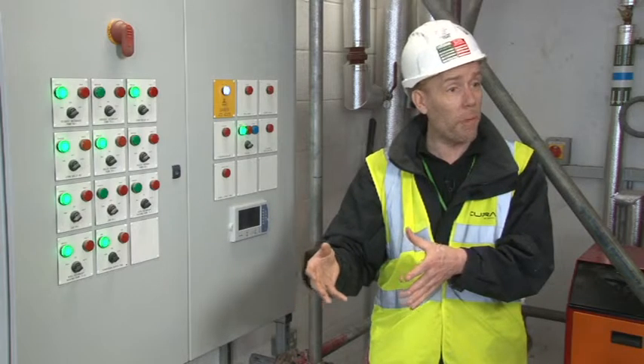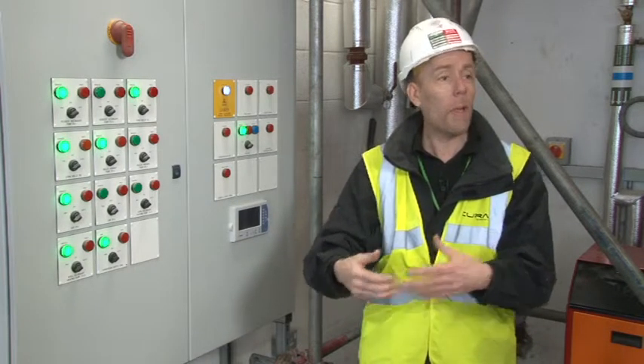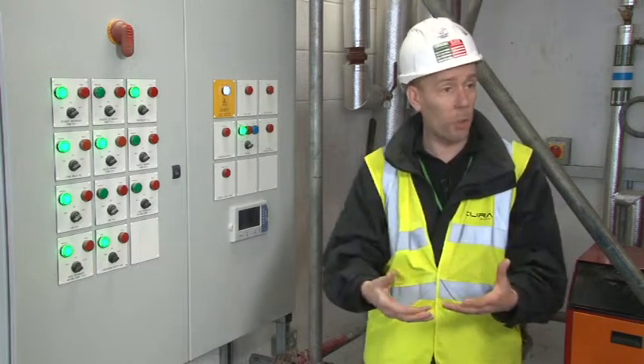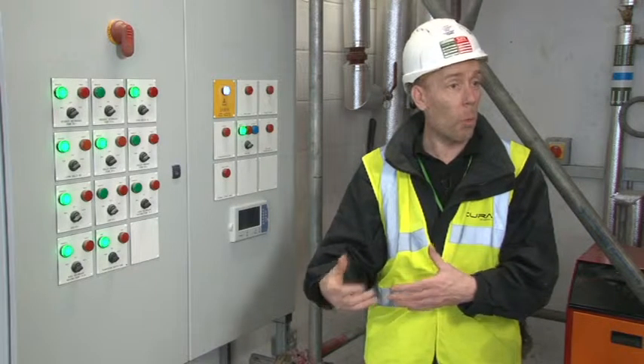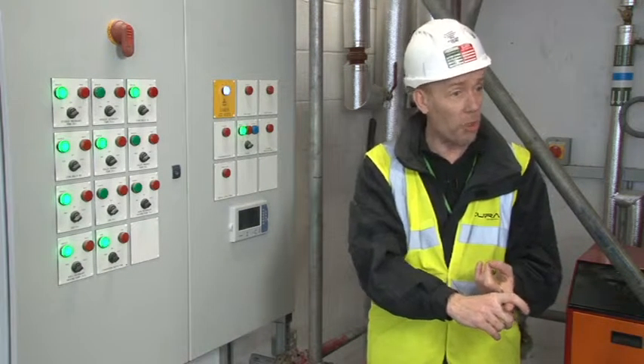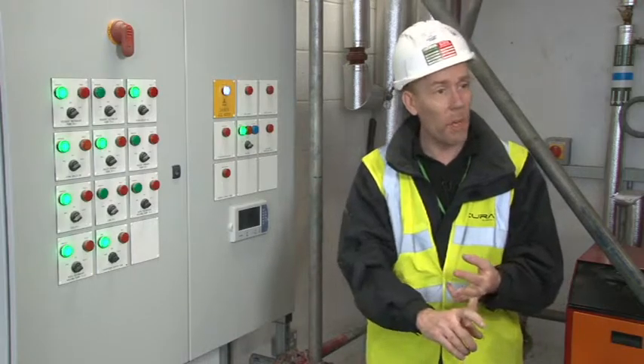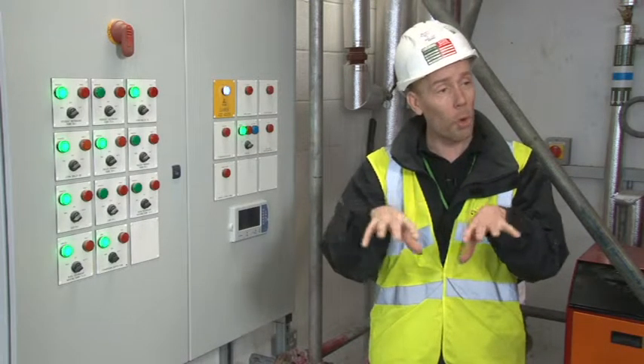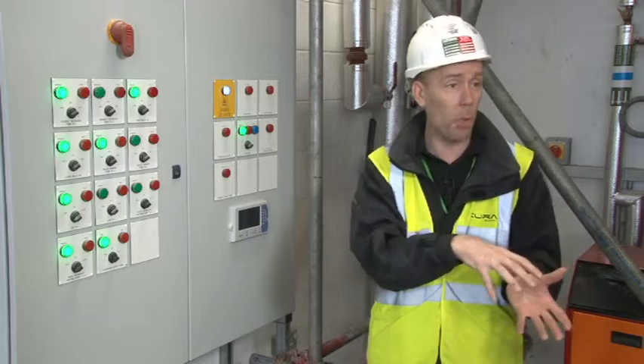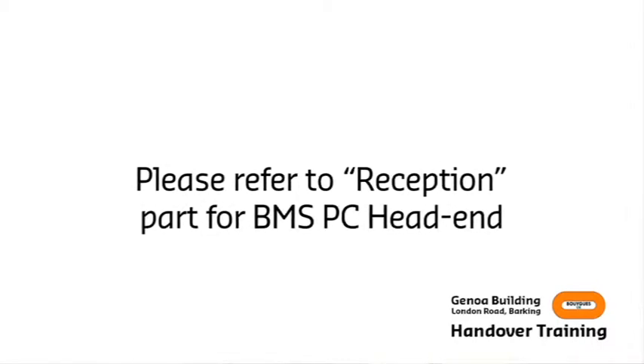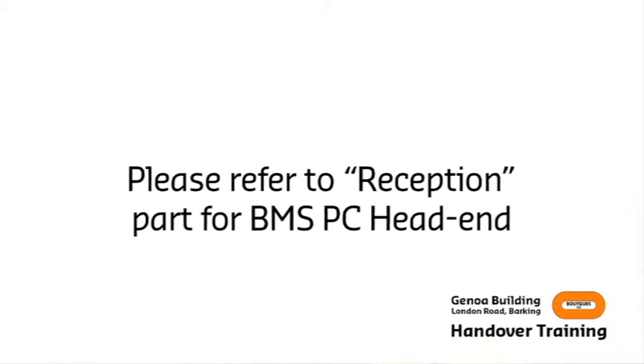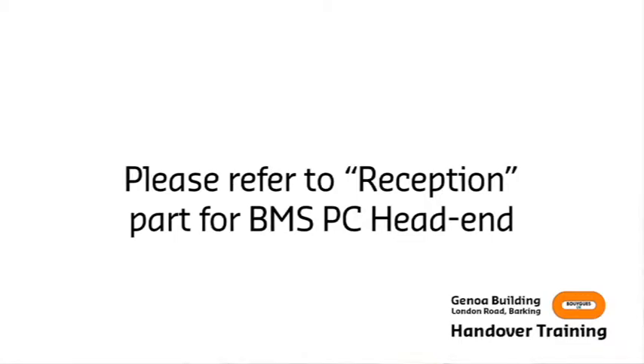Because in future, if there's a constant fault and the installer is called out to rectify that fault, he'll want to know how many times it's been in fault, who reset it, why they reset it, and so on. And all of that can be stored on the head-end computer. There's 2 parts to this explanation, is that we need to go and have a sit with the head-end computer and just explain that as well.